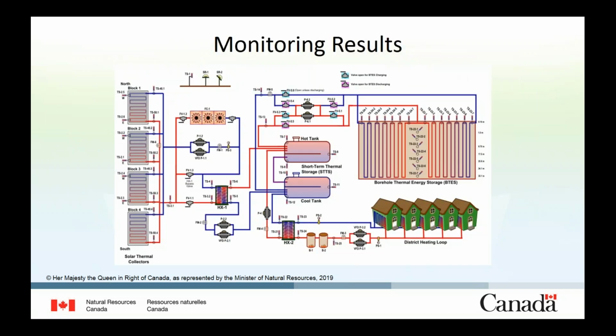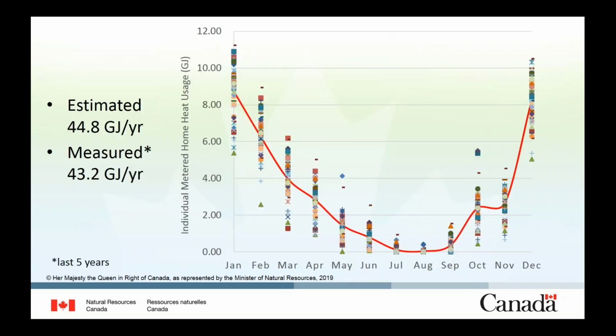This graph shows the individual heat load for each one of the 52 houses. That's the average for the last 5 years. And it's interesting because I have worked on the design of many individual solar space heating and solar water heating systems. What we can see here is that the average is very close to what we had estimated at the beginning of the project. But the individual meter heat usage is quite different. So if those systems were individual, we would have a big problem, but we don't, because we are working on a community scale, and that's the beauty of community systems. That's an interesting point to remember.